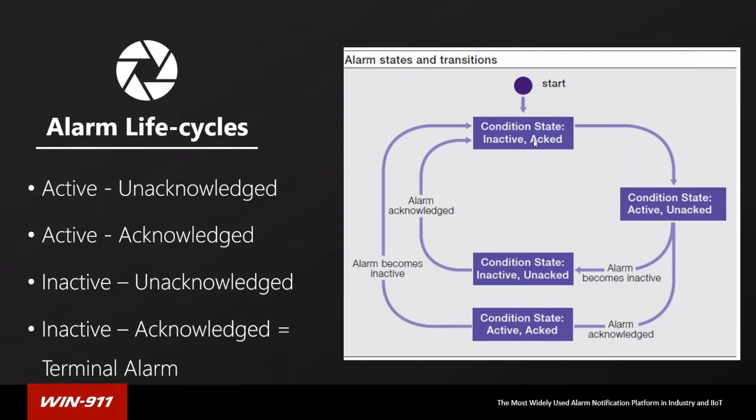And this is typically when the alarm clears from your SCADA, or it will also clear from WIN-911. Now, this doesn't quite apply with OPC because OPC doesn't always have the acknowledgement option, and so typically you can't acknowledge back to OPC from WIN-911. But if we're referring to Rockwell, Factory Talk Alarm and Events, InTouch, System Platform, they all follow this path.